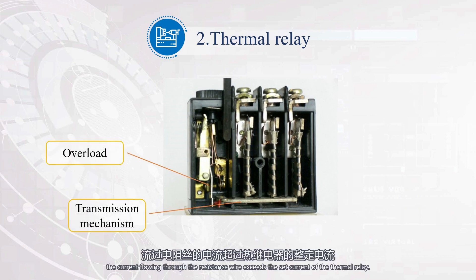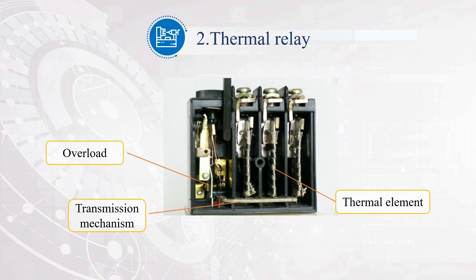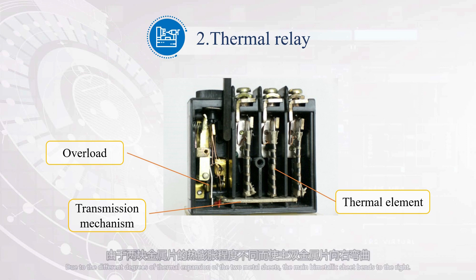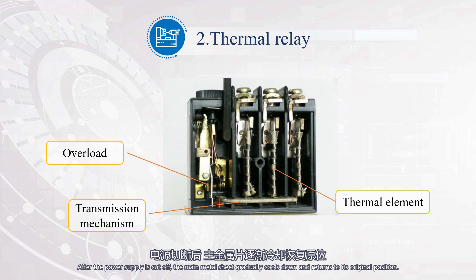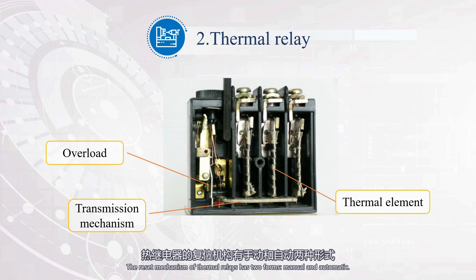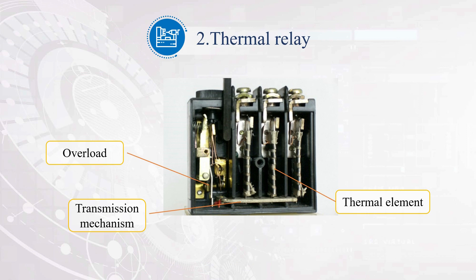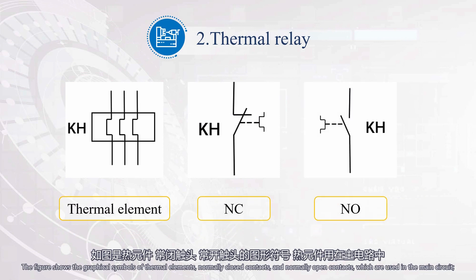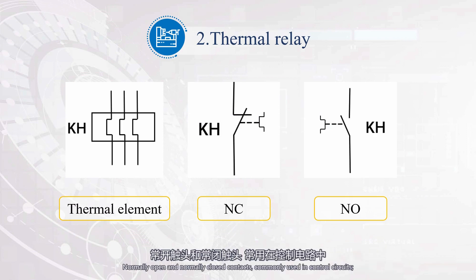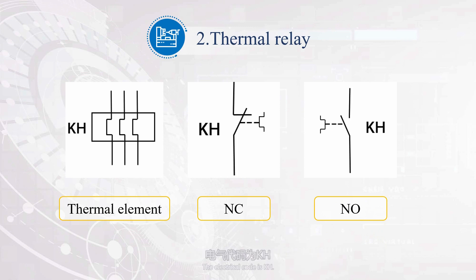When the motor is overloaded, the current flowing through the resistance wire exceeds the set current of the thermal relay. The heat increases and temperature rises. Due to the different degrees of thermal expansion of the two metal sheets, the main bimetallic sheet bends to the right. The transmission mechanism pushes the normally closed contact to disconnect, breaking the control circuit and cutting off the main circuit through the contactor to achieve overload protection. After the power supply is cut off, the bimetallic sheet gradually cools and returns to its original position. The reset mechanism has two forms: manual and automatic. The electrical code is KH.